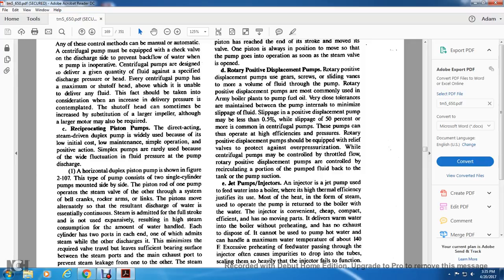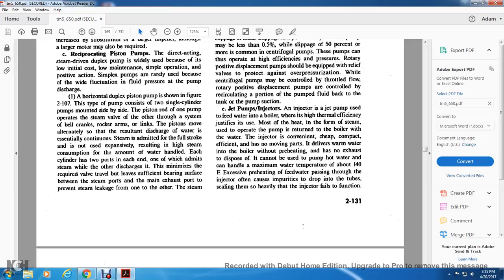Rotary positive displacement pumps should be equipped with a relief valve to protect against overpressurization, while centrifugal pumps may be controlled by throttling the flow. Rotary positive displacement pumps are controlled by recirculating a portion of the pumped fluid back into the tank or the pump suction.